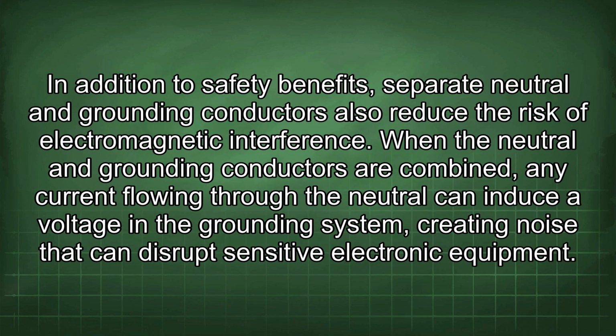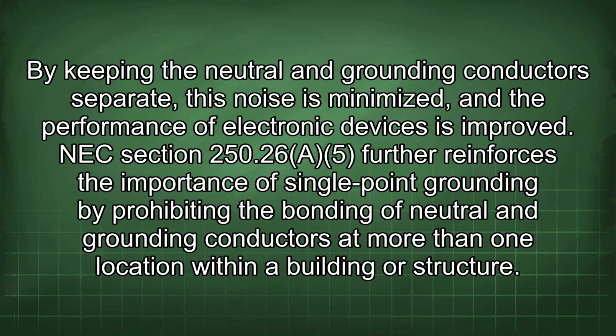In addition to safety benefits, separate neutral and grounding conductors also reduce the risk of electromagnetic interference. When the neutral and grounding conductors are combined, any current flowing through the neutral can induce a voltage in the grounding system, creating noise that can disrupt sensitive electronic equipment. By keeping the neutral and grounding conductors separate, this noise is minimized and the performance of electronic devices is improved.